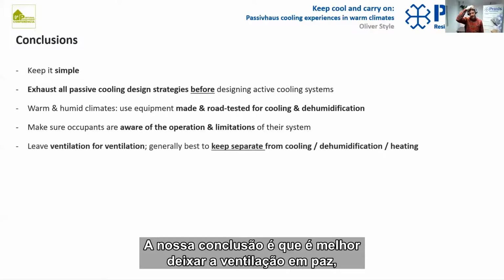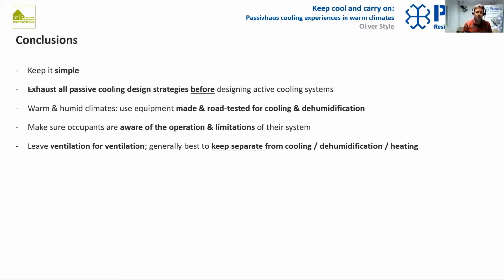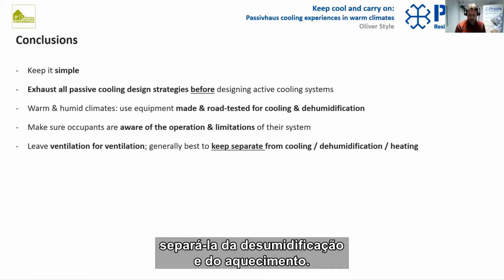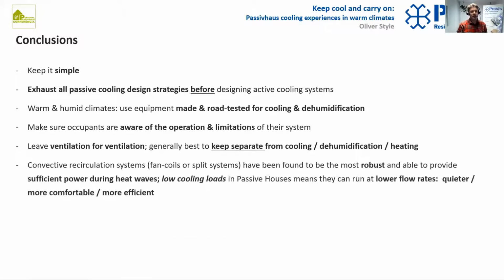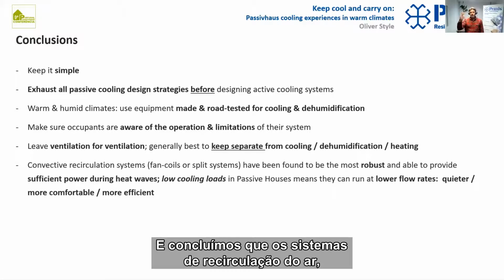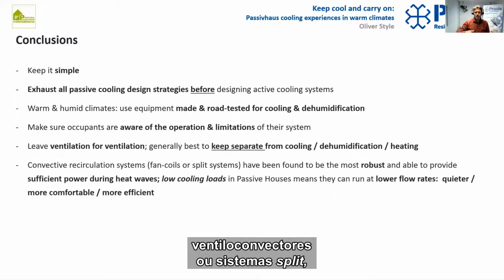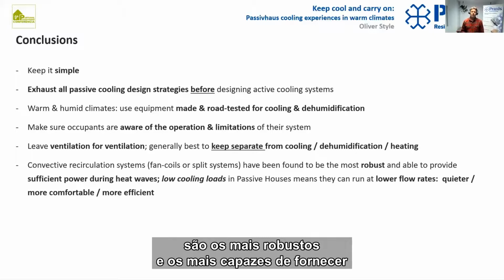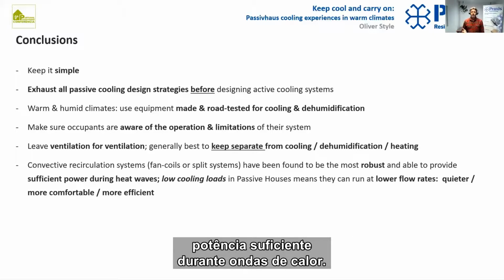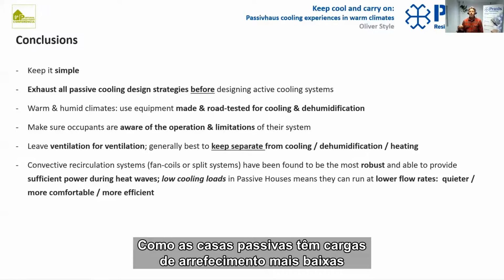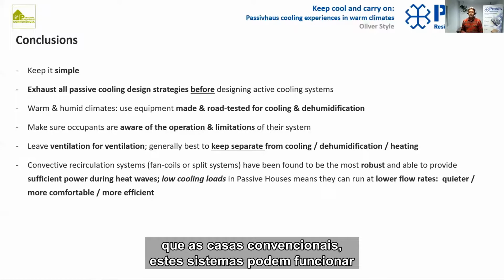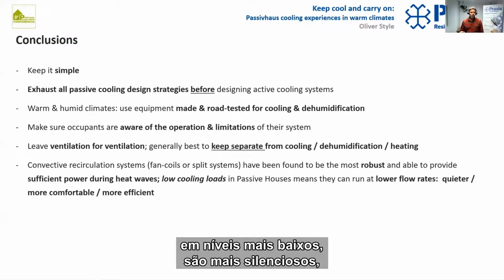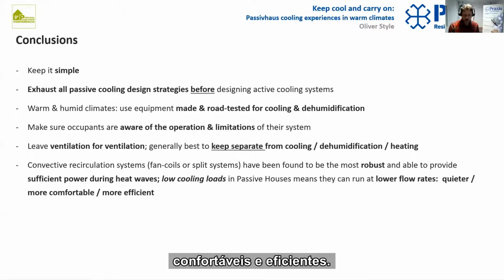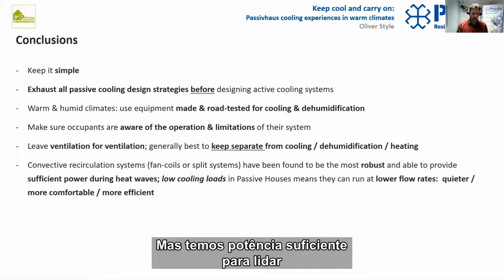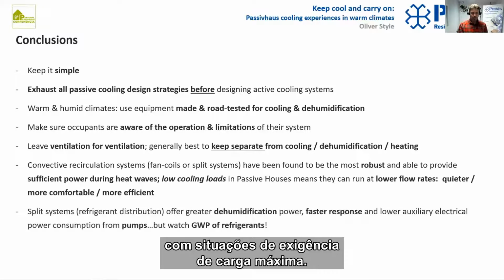Our conclusion is that it's best to leave ventilation for ventilation, separate it from cooling, dehumidification and heating. And we found that convective air recirculation systems, fan-coils or split systems are the most robust and the ones able to provide sufficient power during heat waves. And in passive houses that have low cooling loads compared to conventional houses, that means that they can run at lower flow rates, they're quieter, they're more comfortable, they're more efficient. But you have enough power to deal with peak cooling load situations.